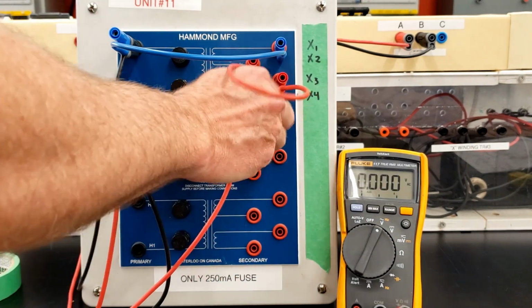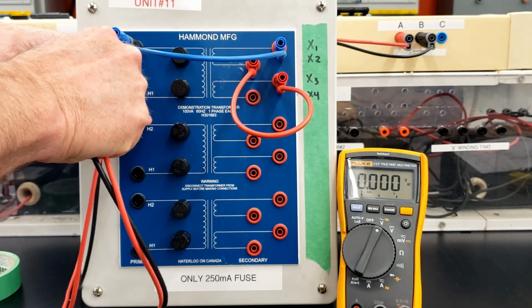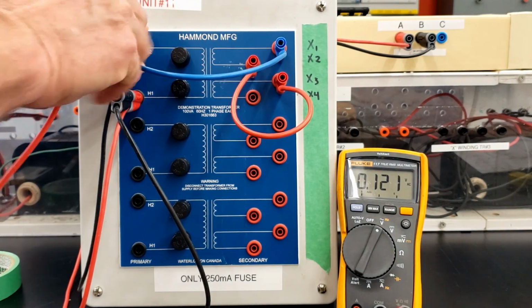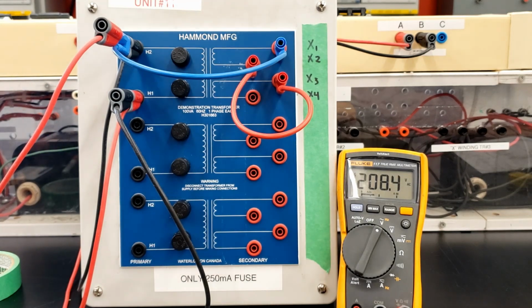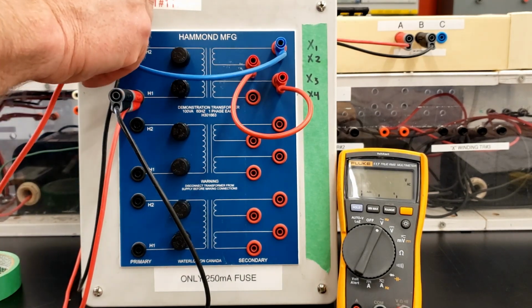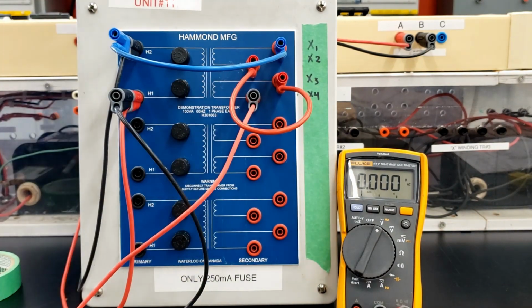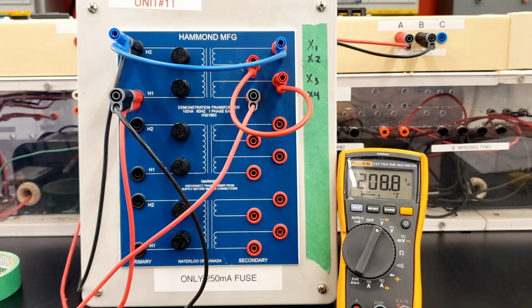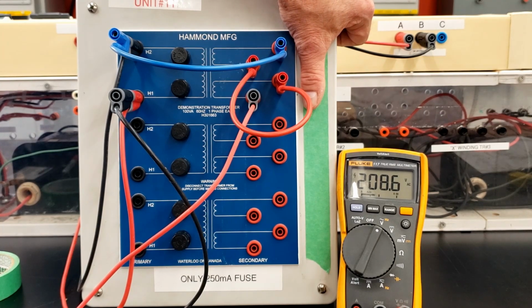So I got 208 volts between those two open connections. If I turn this off and check my primary winding — H1 and H2 — I have 208 volts coming into the circuit, so there's 208 volts on the primary. But once I've put the primary and secondary in series, the sum of the primary voltage plus the secondary voltage is also giving me 208 volts. That means these two must be canceling each other out — this secondary voltage isn't even effectively in the circuit, and the only voltage I'm seeing is my primary voltage.